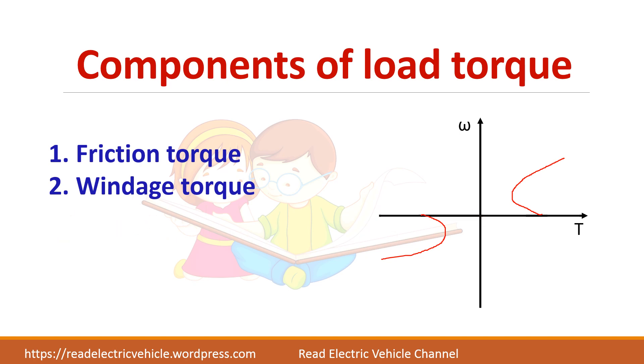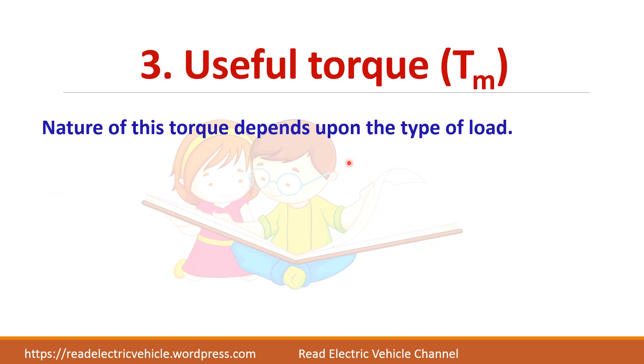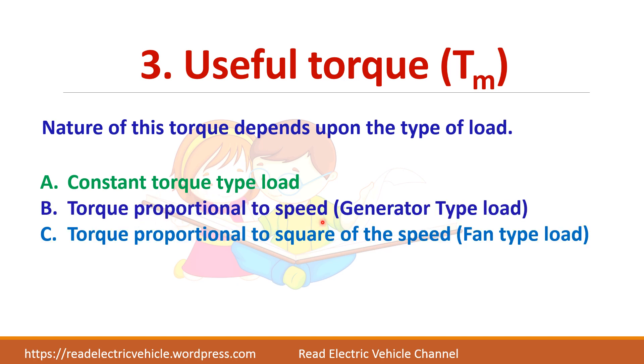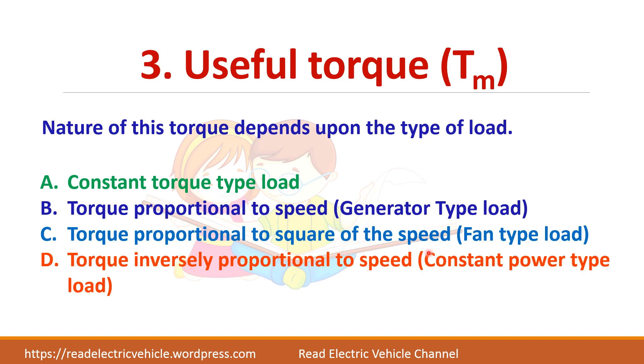One more torque component is the useful torque — the torque that does useful work. The nature of this torque depends on the type of load. Loads can be classified into four types: constant torque load, torque proportional to speed, torque proportional to the square of speed, or torque inversely proportional to speed (constant power load).